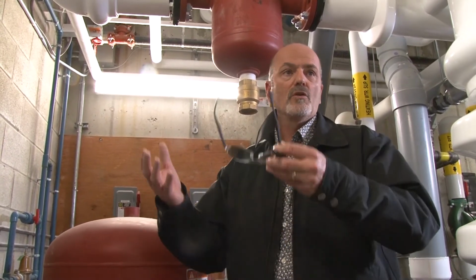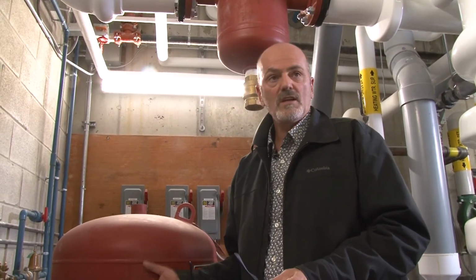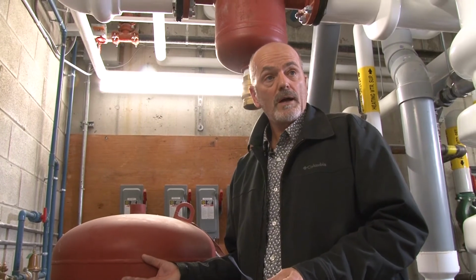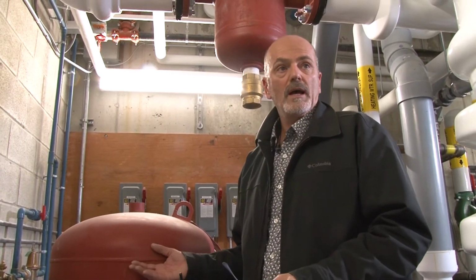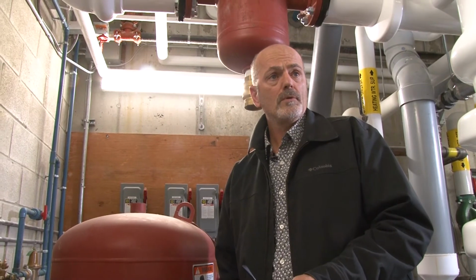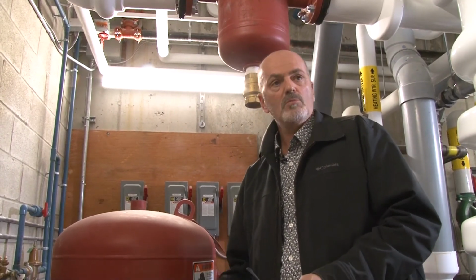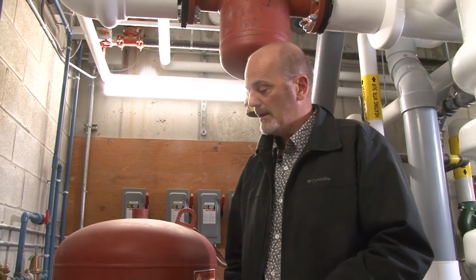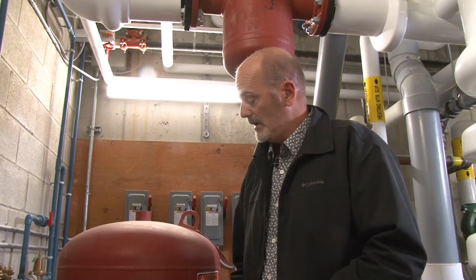So when the system's cold and you first start it up, it will push the bladder so the bladder is pretty much empty, and all the system fluid is out in the system. As the water heats up, starts to expand, that starts pushing back and fills up the bladder. And that's what's known as acceptance volume. Okay, it accepts that fluid, fills the bladder, but maintains a closed system and then pushes it back as the system cools. And that's a constant thing. It'll move up and down over time as it heats up and cools down, okay? And that goes for all the tanks in the system.